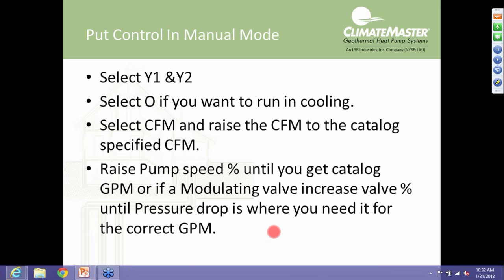Now, if you happen to have to run the pump outside of 50 and 90% and you cannot see GPM on the screen, we'll then have to take a pressure drop reading. Or if you have a modulating valve, you must take a pressure drop reading because you will never see GPM on the screen. Now, to do the pressure drop, we do not use the PT ports that we typically put on the front of these heat pumps. We now have attached to the front right-hand corner post of the heat pump down by the water connections, both a pressure in and a pressure out pressure port that's actually an automotive Schrader port. So just like on your car tire, we recommend get a digital tire pressure gauge and measure pressure in and pressure out, take the difference, and we have to use the chart in the installation manual and convert that to gallons per minute.